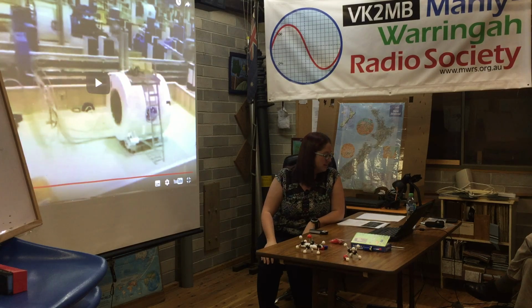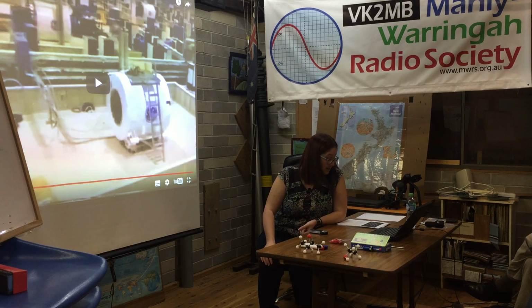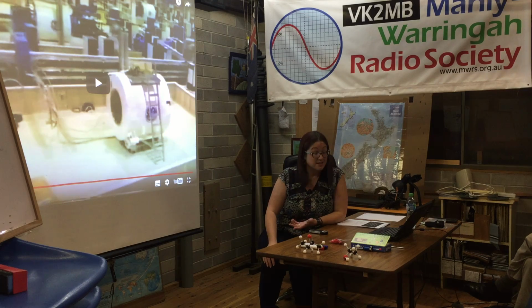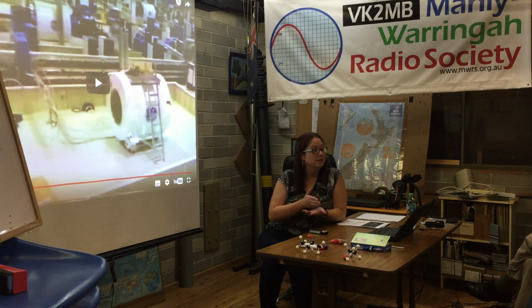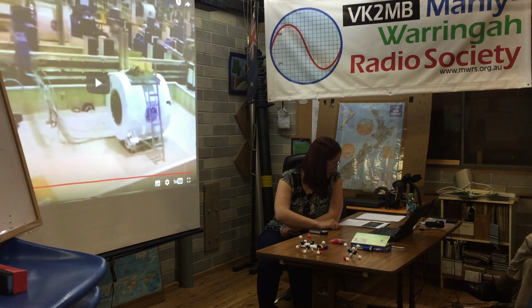It also mentioned the fact that the fields were in excess of the kind of magnetic field that's generated by an electromagnet in a junkyard. Those tend to be of the order of 1 Tesla. A typical MRI is 1.5 Tesla. There are some 3 Tesla magnets in use. There are also 7 Tesla MRIs, but those are for research only. They're not used clinically. And so a modern 1.5 Tesla magnet would be 60,000 times Earth's magnetic field at the centre of the bore, not 25,000. So the technology has moved on quite a bit since this video was made.